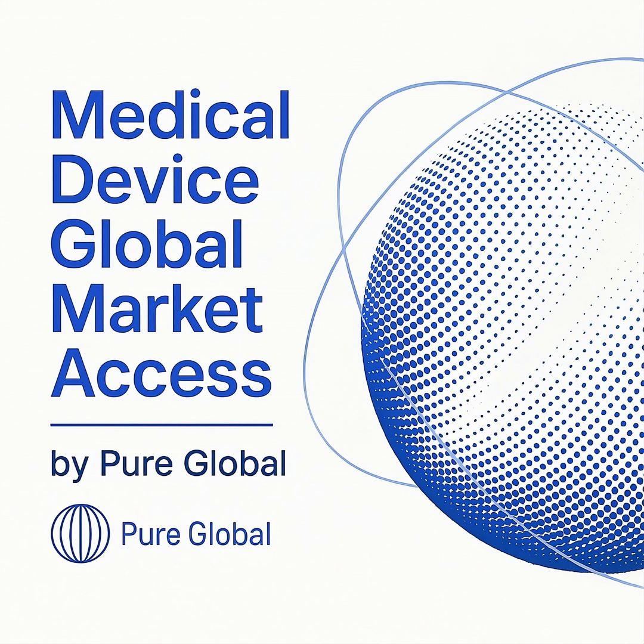Furthermore, this new focus places a heavy burden on version control and change management. When you push an update, you are effectively placing a new version of your medical device on the market. Your quality management system, or QMS, must have robust procedures for managing these software updates, including how changes are validated, documented, and communicated to users. It is the manufacturer's responsibility to ensure that only the current, compliant version of the software is available for new downloads, and to have a plan for managing older versions that may still be in use.